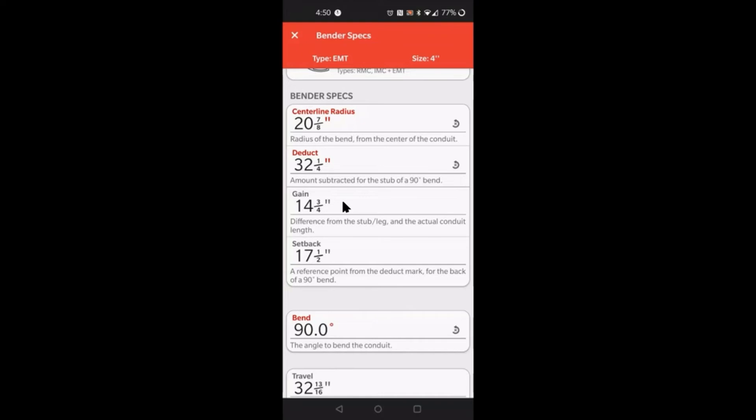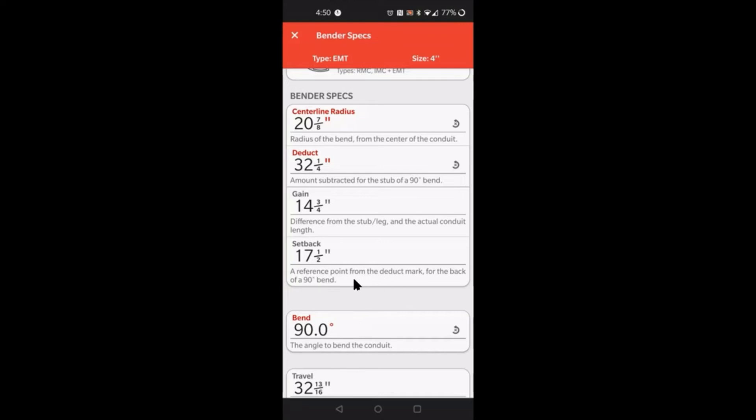Next is the setback, one of my favorites. This right here is a time saver. If you're working with large conduit, you're going to actually thank me. Basically what the setback is, one of the reasons you want to use it is it's a reference point from the back of the 90 to the stub mark. Let's just say for an example you wanted to do a 90 degree bend with a kick 20 inches from the back of the 90.